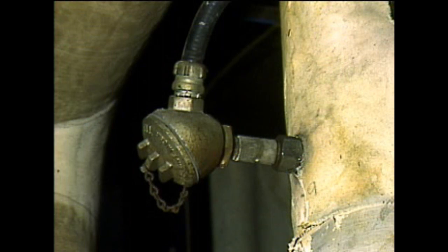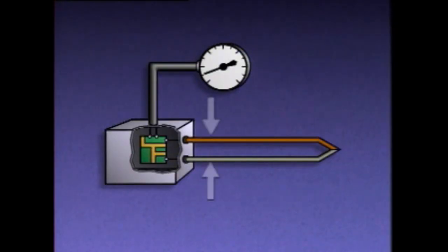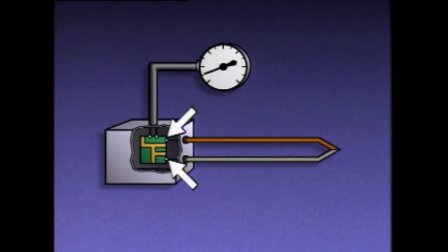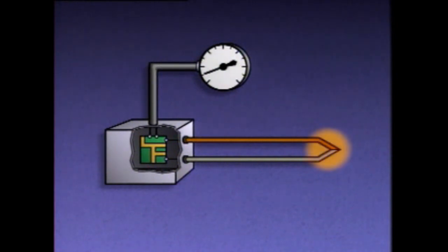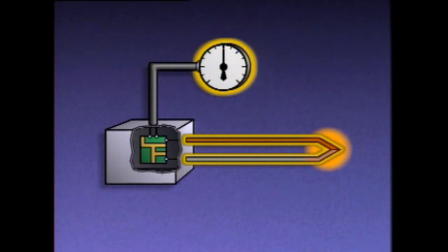While many temperature indicators are mechanical devices, some, like this thermocouple, are thermoelectric devices — they convert heat into electricity to measure temperature. A thermocouple consists of two wires of different metals joined at one end. The opposite ends of the wires are connected to an electronic circuit, which in turn is connected to an indicator. When heat is applied to the joined ends, a small voltage is generated in the wires. The electronic circuit detects the voltage and converts it to a corresponding temperature.